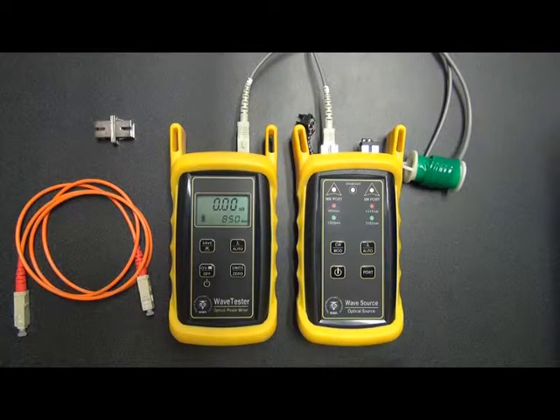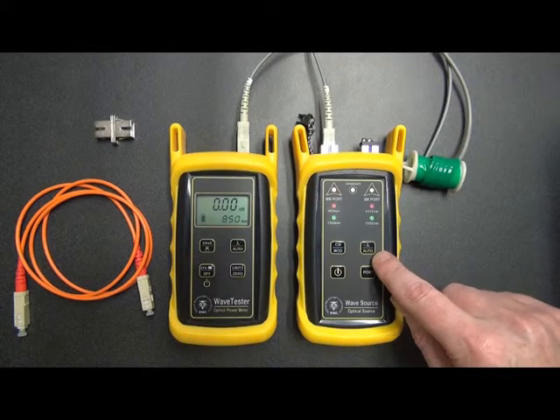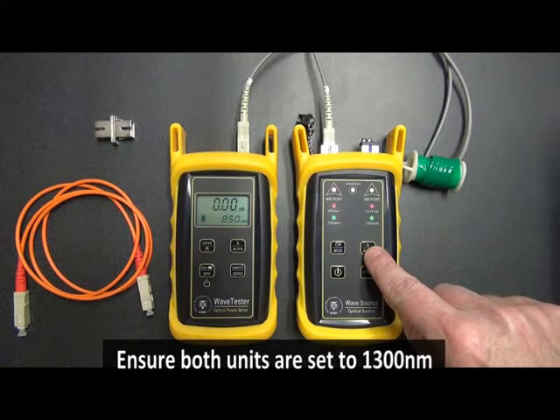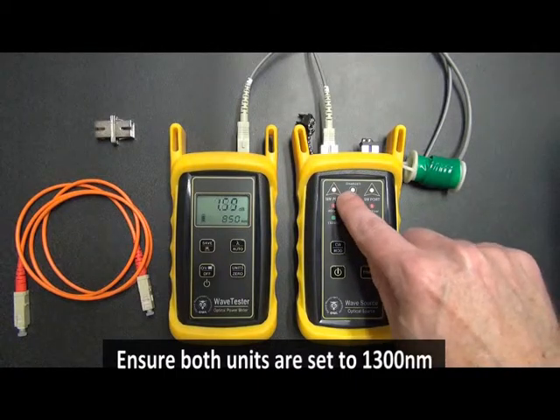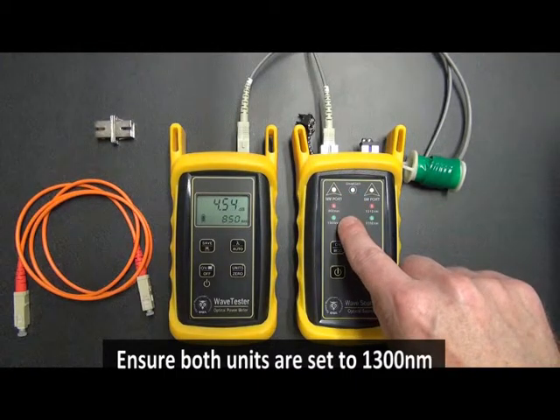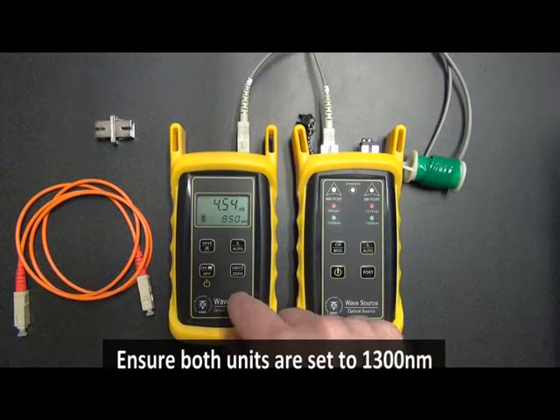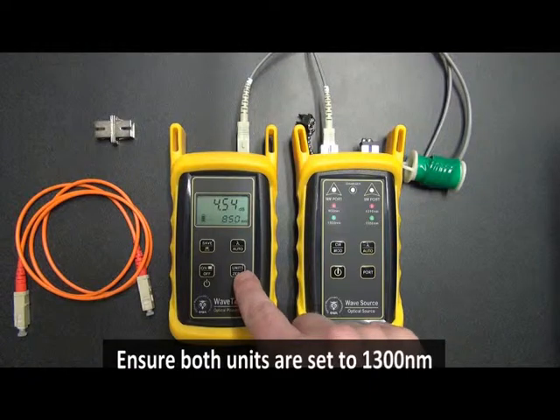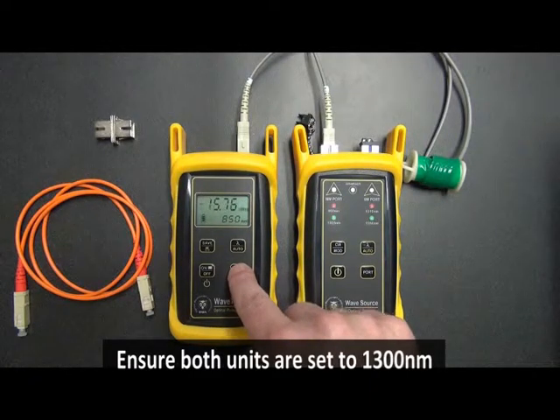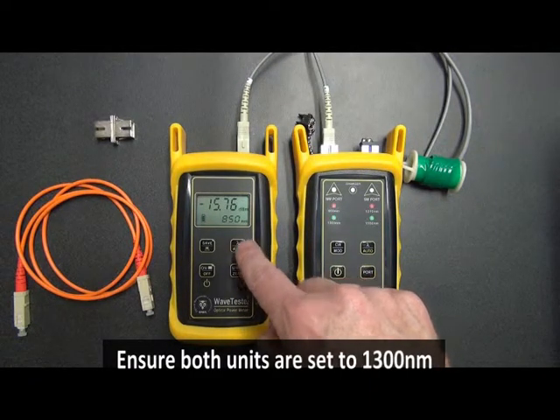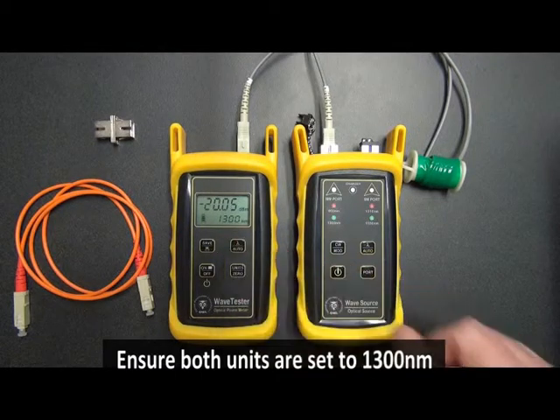Now, it's always a good idea to check both wavelengths, especially if we're doing a dual wavelength test. In this case, 1300 is the second wavelength. So what we want to do, first of all, is press the wavelength button on the WaveSource. We'll notice it flashes briefly and then goes to green. Okay, now what we want to do is make sure that we change our units back to dBm, and then we also change the wavelength to 1300.